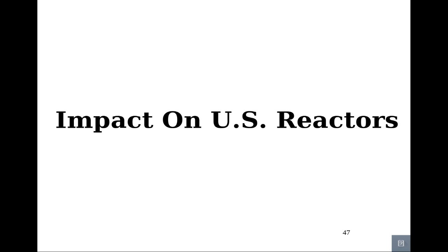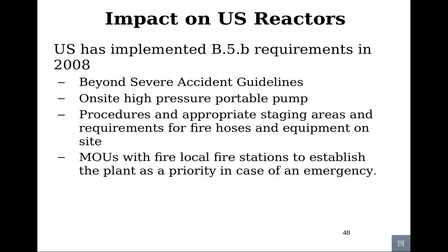Impact on United States reactors. In 2008, the NRC established the B.5.b requirements to defend against beyond design basis accidents. It requires the procurement of high-pressure portable equipment designed to enable core cooling with the loss of all off-site as well as on-site backup power. It also establishes memorandums of understanding with local fire stations to establish the plant as a priority in the area. Unfortunately, these requirements were considered top secret and were not adequately conveyed to the Japanese nuclear fleet.